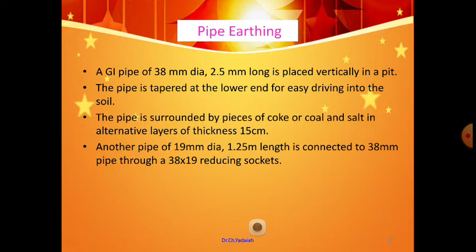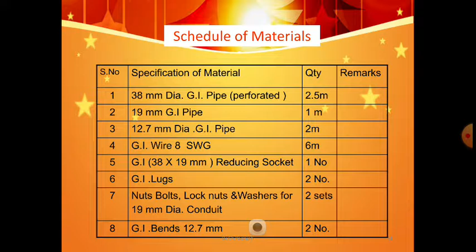38 mm dia GI pipe, perforated, 2.5 meters depth, and the 19 mm GI pipe, which we already know. 12.7 mm dia GI pipe, 2 meters. GI wire 8 SWG, standard wire gauge, 6 meters, and a 38 into 19 mm GI reducing socket, one number. GI lugs 2 numbers, nuts and bolts, lock nuts, washers, and 19 mm dia conduit 2 sets, and GI bends 2 numbers. 30 into 30 centimeters cast iron frame with hinges 1 number, 30 into 30 centimeters cast iron cover 1 number, funnel with wire mesh 1 number, charcoal or coal 20 kgs, and salt 20 kgs, and cement concrete, a lump sum, as much as required.